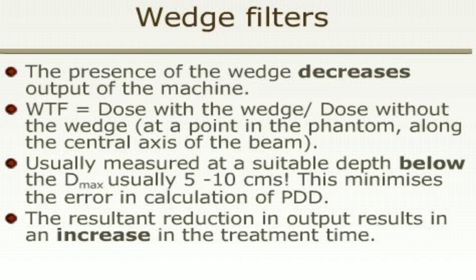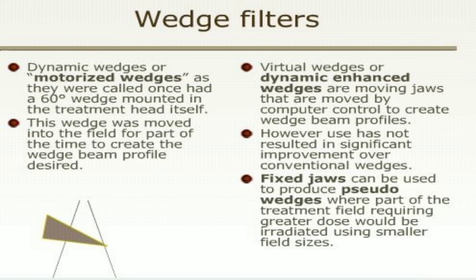Dynamic wedges, or motorized wedges as they were once called, use a 60-degree wedge mounted in the treatment unit itself. This wedge is moved into the field for part of the time to create the desired wedge beam profile. Virtual wedges or dynamic enhanced wedges are moving jaws controlled by computer to create a wedge beam profile; however, their use has not resulted in significant improvement over conventional wedges. Fixed jaws can be used to produce pseudo wedges, where the part of the treatment requiring greater dose is irradiated using a smaller field size.